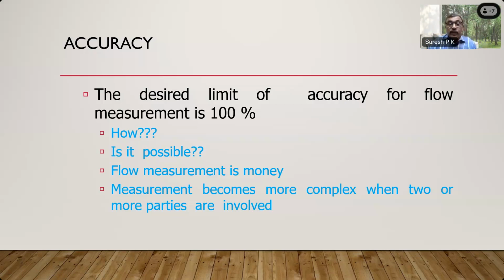Flow measurement is money in many cases, and measurement becomes more complex when two or more parties are involved in the measurement. The parties never agree with each other's measurement. Sometimes one party has a meter, another party has another check meter in line. You have two readings and you have a controversy. Sometimes they put a third meter also and you have pandemonium. These three meters never agree with each other. Everybody will say my meter is accurate. So the verification of the meter with a common system will probably solve the problem.